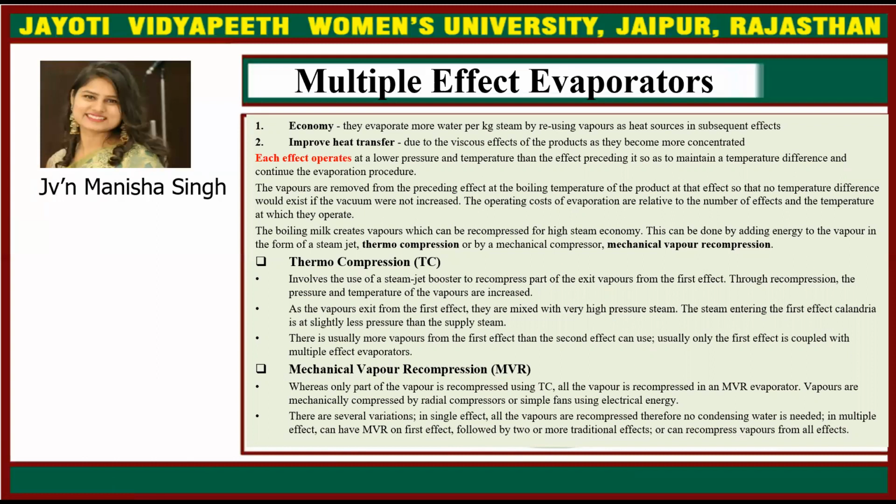Then what are the advantages of multiple effect evaporators? First is economy. They evaporate more water per kg of steam by using vapors as heat sources in the subsequent effects, as I mentioned in the previous pictures, and they improve heat transfer despite the viscous effects of the products as they become more concentrated. Each effect operates at a lower pressure and temperature than the effect preceding it, so as to maintain a temperature difference and continue the evaporation procedure. The vapors are removed from the preceding effect at the boiling temperature of the product at that effect, so that no temperature difference would exist if the vacuum were not increased. The operating costs of evaporation are related to the number of effects and the temperature at which they operate.